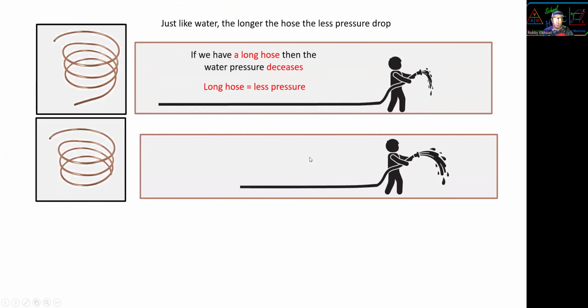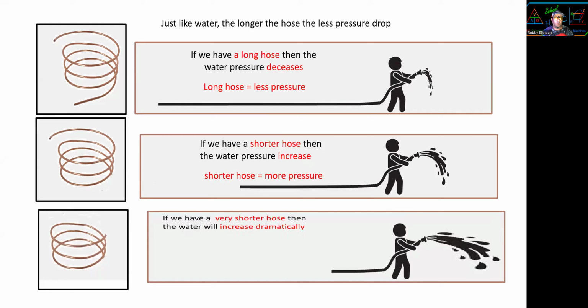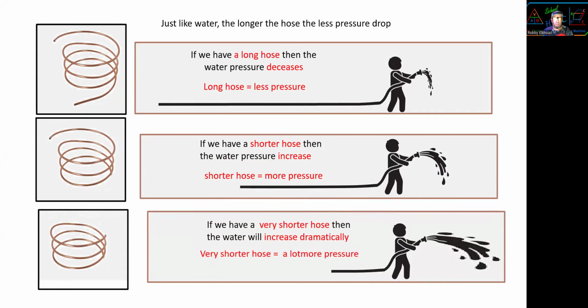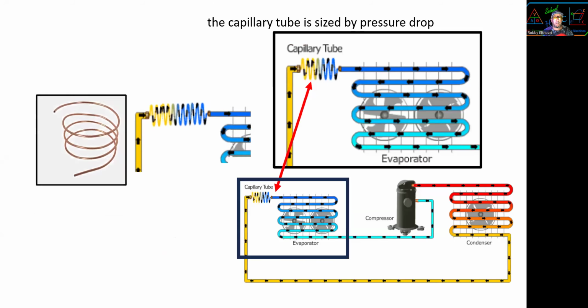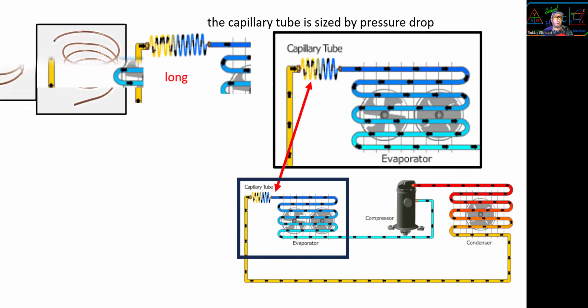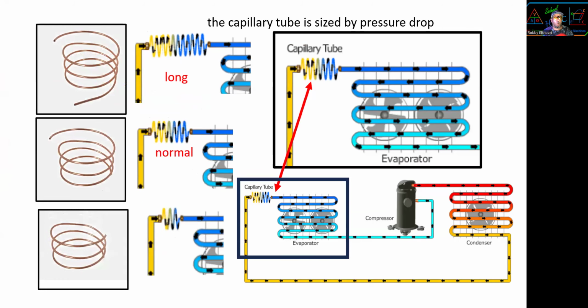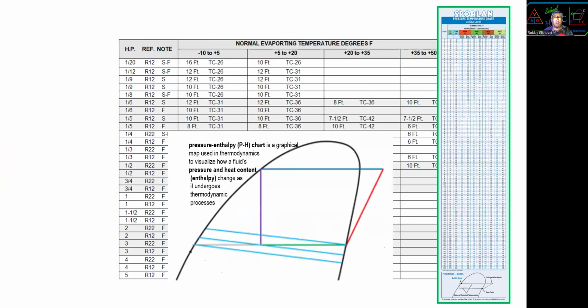We have a long hose, water pressure decreases. Long hose, less pressure. We have a shorter hose, the water pressure increases. Shorter hose, more pressure. We have a very short hose, the water will increase dramatically. Very short hose, a lot more pressure. Similar to capillary tube. The capillary tube, long, normal, or small, will affect the low pressure.